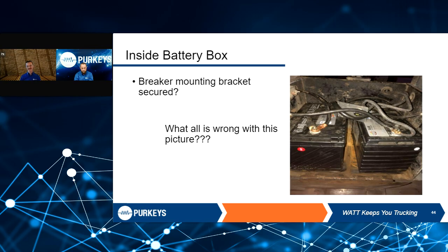Big scary thing is the 30 amp breaker in that metal bracket floating around, just waiting to ground out inside of this battery box. This also looks like an older metal battery box as well. So yeah, lots of things to short out on in here. Overall cleanliness too. This thing just needs to be torn apart, cleaned up. If it gets this bad, guys, Purkeys does have a full replacement battery box system ready to bolt on to the trailer. At this point, I'd say start fresh.